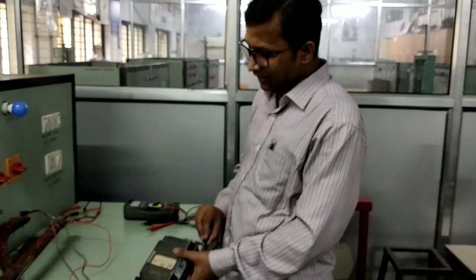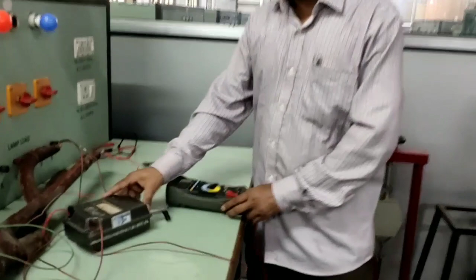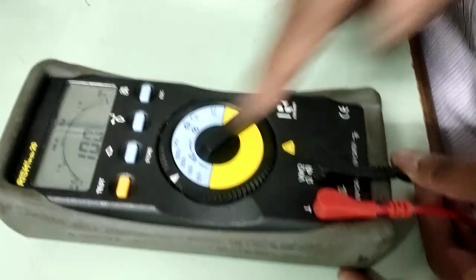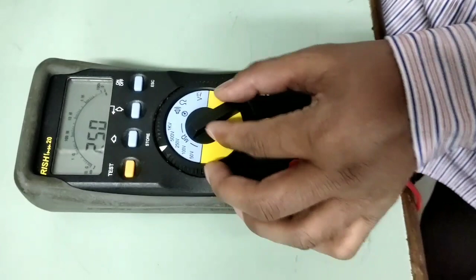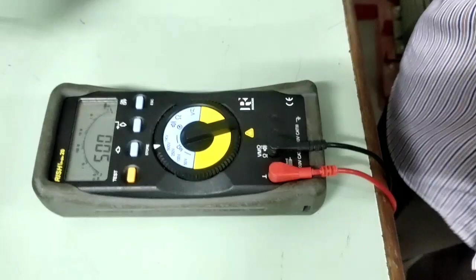And this is an old instrument that is called a Megger, as you know. Nowadays, a digital type insulation meter is there in the market, and we have this type of meter also. This is called a digital insulation tester. Okay, the scale is there, the same test point is there. You can select voltage 50 volt, 100 volt, 250 volt, 500 volt, 1K. Means it is the voltage generated in this meter to measure insulation resistance of the cable. I will select 500. Okay, this meter can be used to measure continuity also, to measure resistance, and AC and DC voltage also.